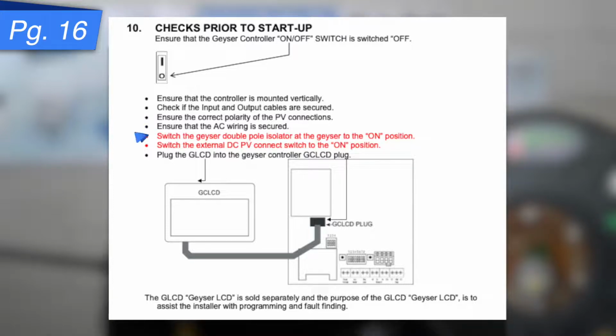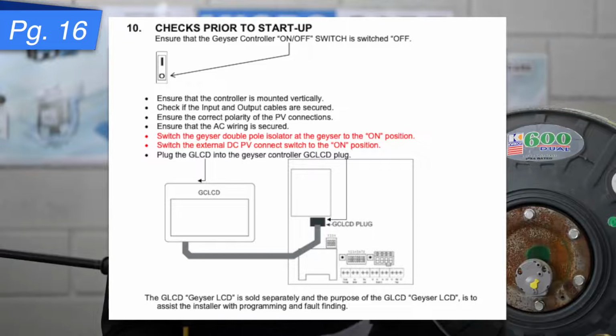Now, switch the geyser double pole isolator at the geyser to the on position. This is the isolator in the roof next to the geyser. Then switch the external DC PV disconnect switch to the on position. So this is now between that isolator I mentioned earlier and all the way to the geyser controller.